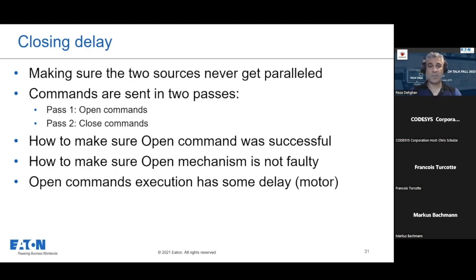We first send the open commands and we wait for the confirmation. This is just to make sure at least one breaker would be open in the branch, and then we start sending the close commands. How to make sure an open command was successful? How to make sure the open mechanism is not faulty? Because if you send a command and you don't wait for a confirmation, you can never understand if it was okay. And then if you start closing and for some reason the open didn't happen, that could lead to a big explosion.